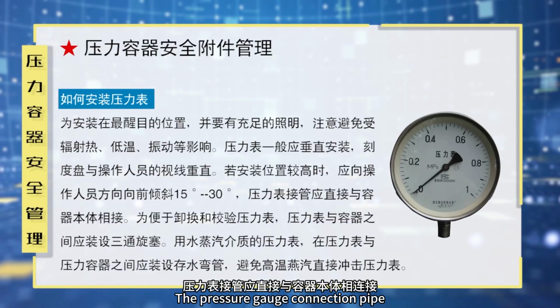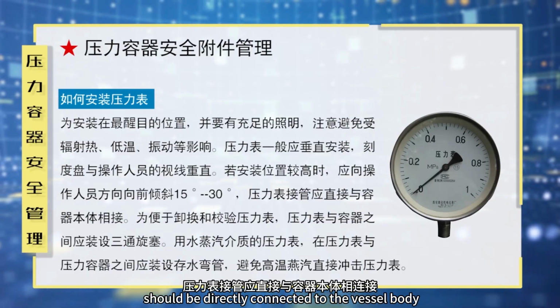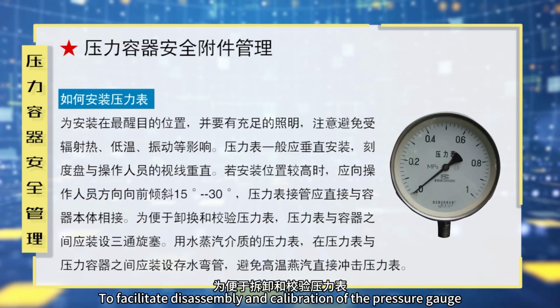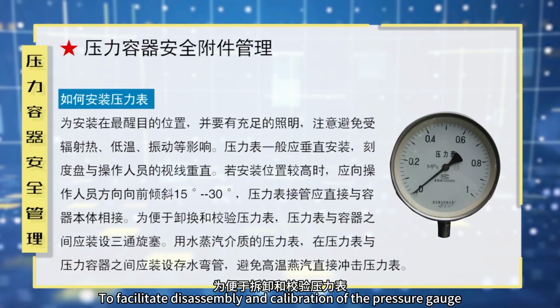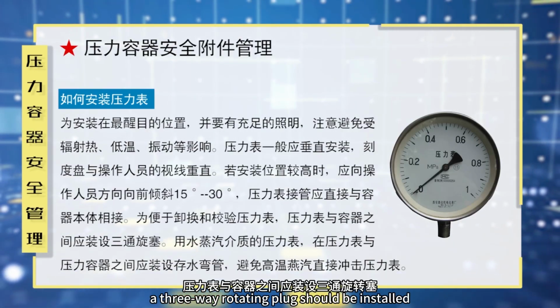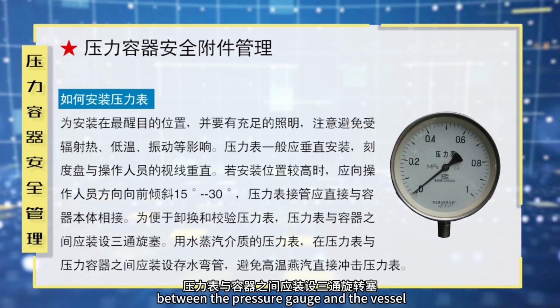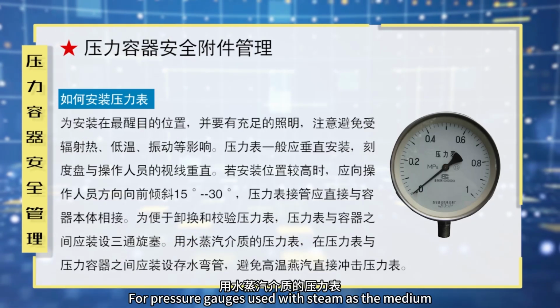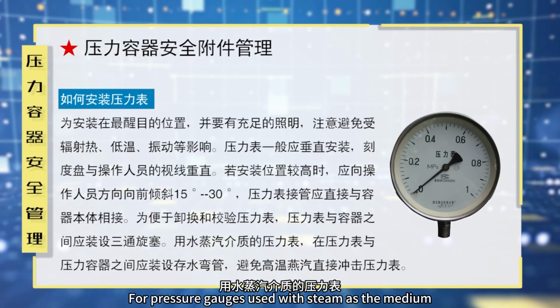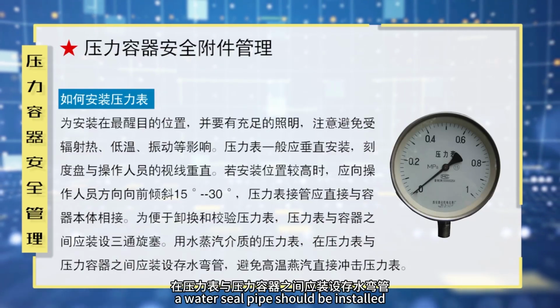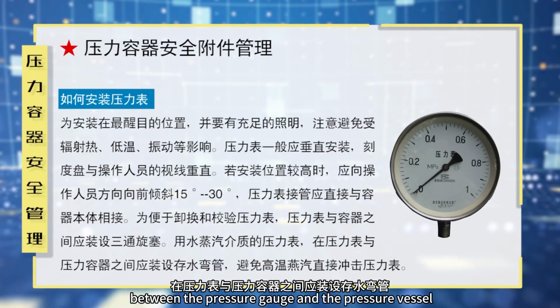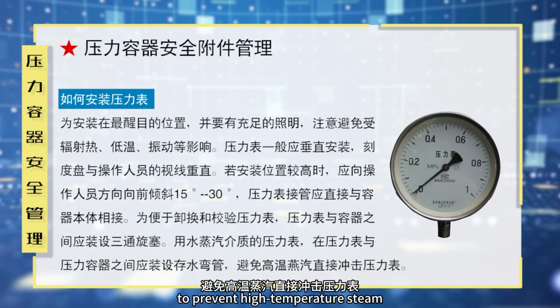The pressure gauge connection pipe should be directly connected to the vessel body. To facilitate disassembly and calibration of the pressure gauge, a three-way rotating plug should be installed between the pressure gauge and the vessel. For pressure gauges used with steam as the medium, a water seal pipe should be installed between the pressure gauge and the pressure vessel to prevent high-temperature steam from directly impacting the pressure gauge.